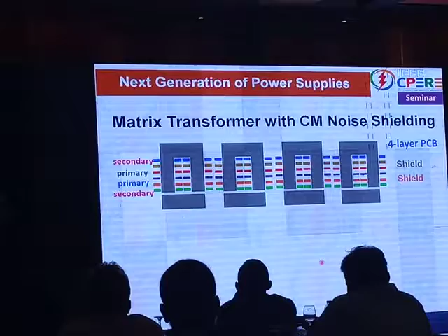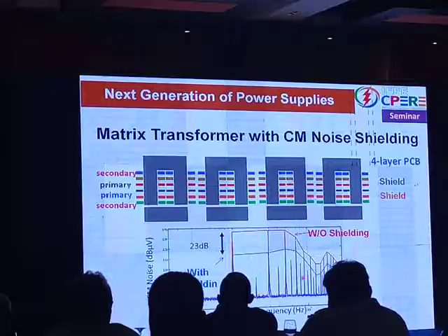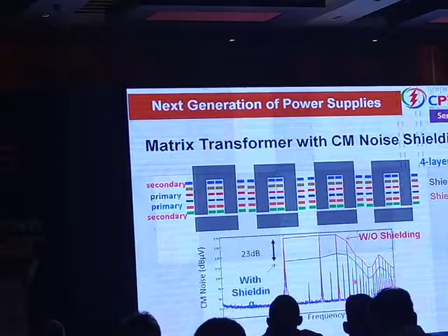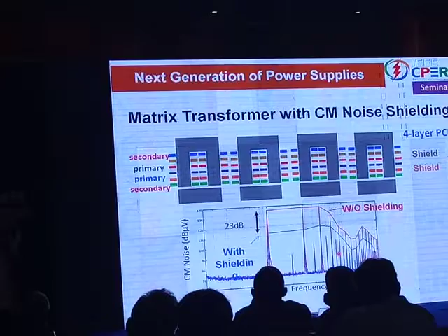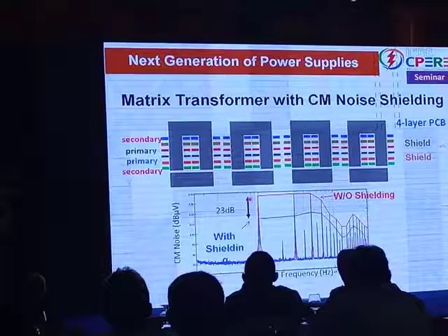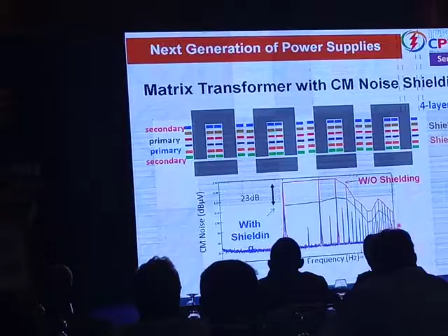What you can do is put 2 shield layers between the primary and the secondary. When you do that, you completely block the common mode noise going through the transformer — it gets terminated and blocked. You get a common mode noise reduction of 23 dB from 150 kilohertz all the way up to 30 megahertz. Nobody has ever been able to do that before.